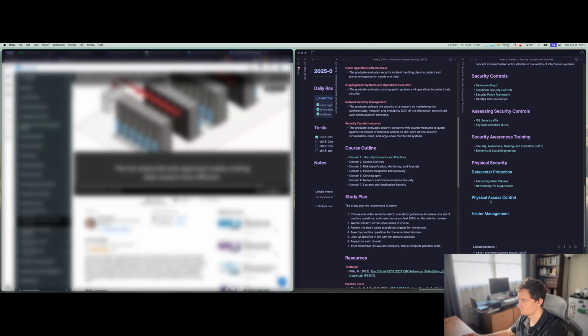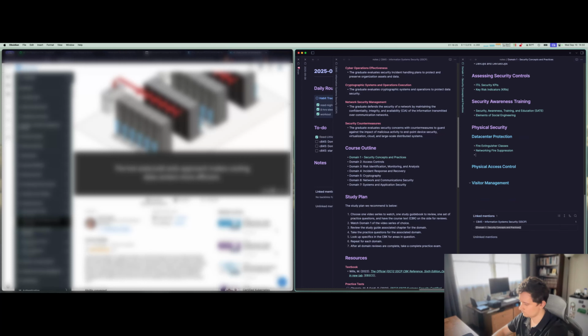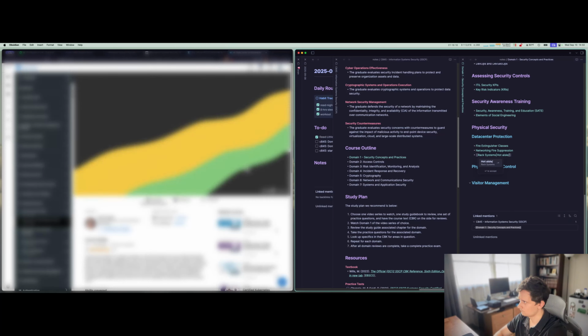Laid out in this way, aisles alternate purpose between being a source of cold air or an exit point for warm air. HVAC designers can use this to their advantage, pumping cool air into the cold aisle and pulling warm air out of the hot aisle.